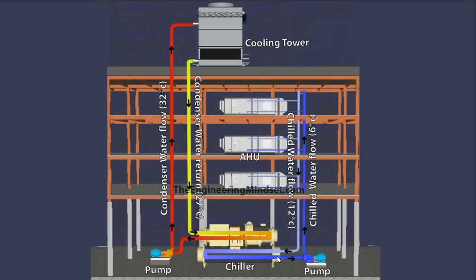And the only way to do that is to compress everything, compress all the particles, raise that temperature, get the energy in a much denser form so that it can be moved more efficiently, and we can transfer that heat. If the refrigerant entering into the condenser was at the same temperature, say it entered at 27 degrees Celsius, you wouldn't reject any heat and the chiller would not work.